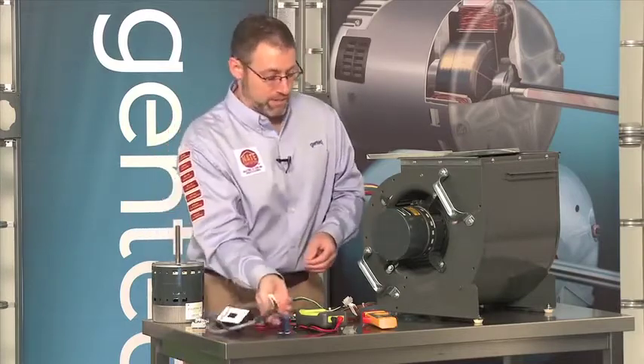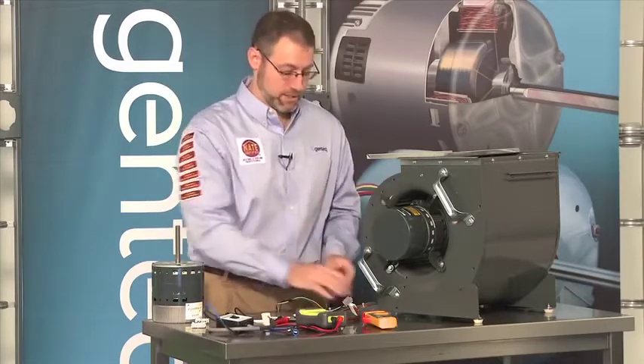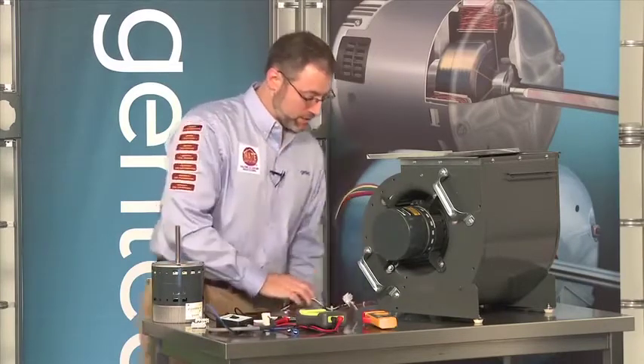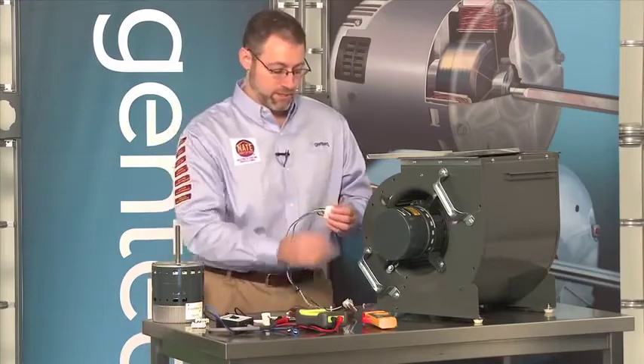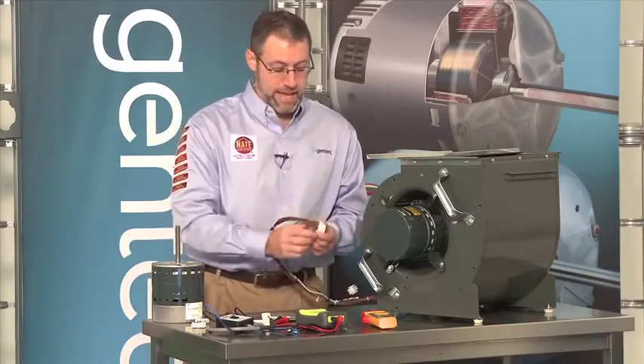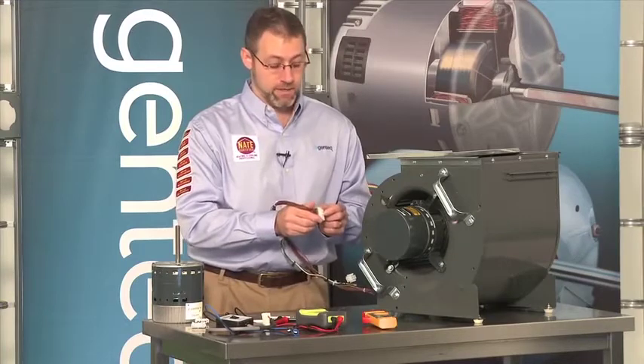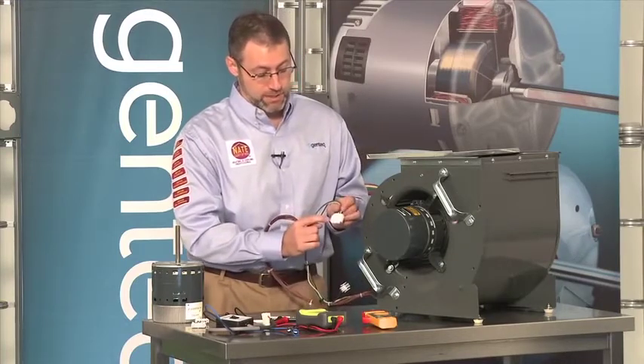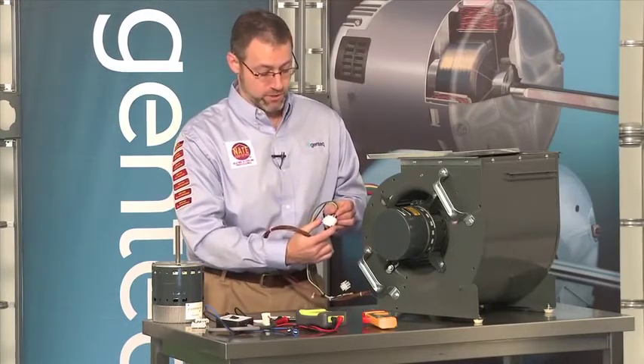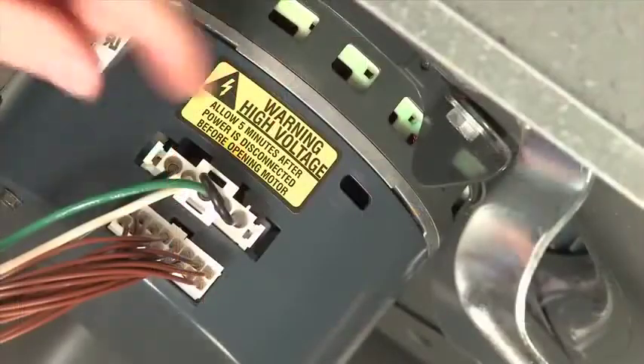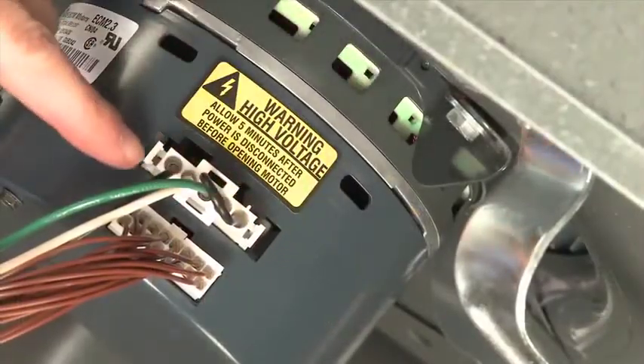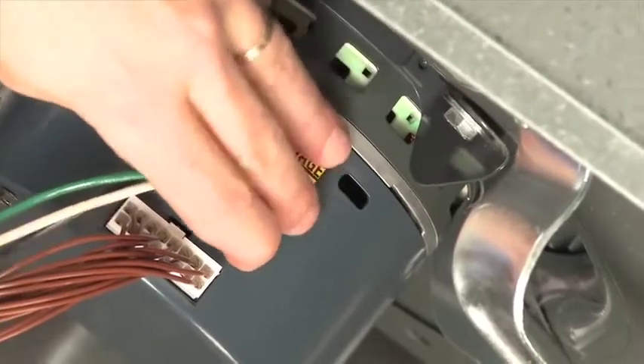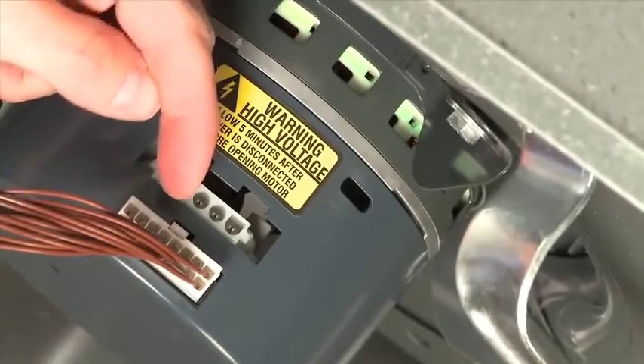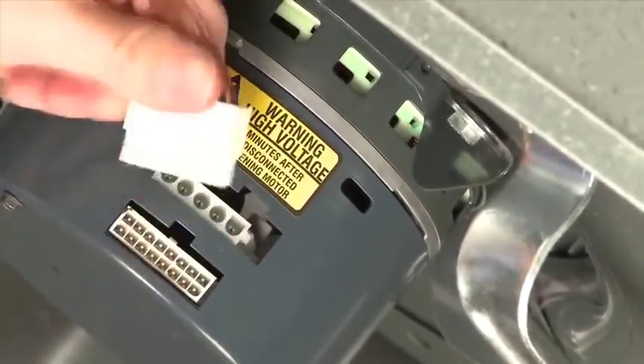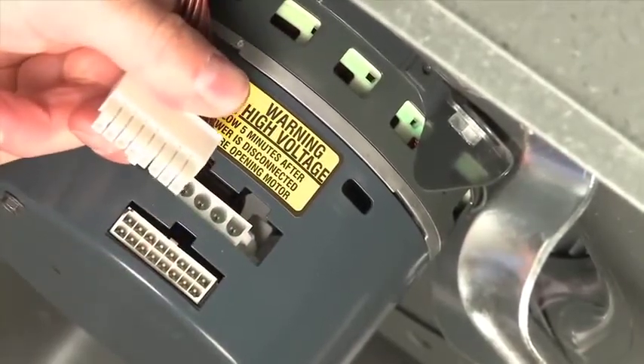So to use the TECMate, we obviously have to disconnect the communication connector. And it's worth noting that the communication connector's latch is on the inside, whereas the high voltage plug latches, I should say, are on the outside. So when they're connected in the motor, it's very difficult to only disconnect the communication connector. It's much easier, of course, after you've turned the power off, to disconnect the high voltage plug and get it out of the way, and then disconnect your communication connector.